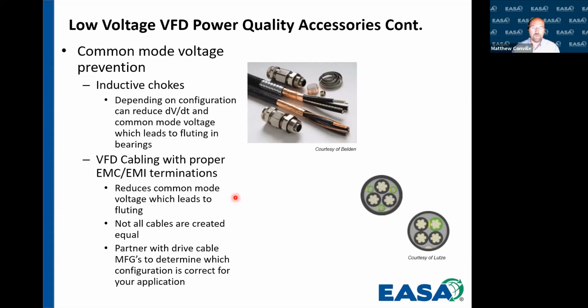It's actually going to take that high frequency voltage that we'll see, and it's going to dissipate it straight to the frame before it ever gets a chance to go to the motor shaft. One of the things that we need to understand is that not all variable frequency drive cable is created equal. So we may not want to use that, you can't just go pick one and that's going to work in every application. You want to make sure that you pick the one that's appropriate for your application and for the horsepower of the machine. The cable manufacturers, they will work with you to determine what's best for your application.